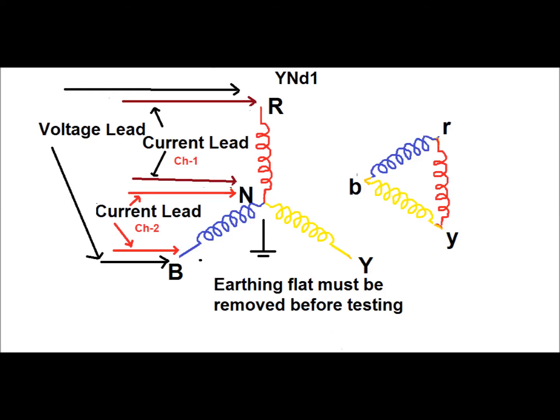Now, how two phase resistances can be measured simultaneously for a Y connected transformer in the test kit is shown in this diagram. Here the potential input channel, that is the voltage lead, has one terminal connected to one phase and the other terminal to the other phase. The voltage lead is connected between the R and B phase leads, one current channel input is connected between R and N, and the other channel's current lead is connected between blue and N. Here channel 1 and channel 2 will show the resistance of the R phase winding and the B phase winding respectively.